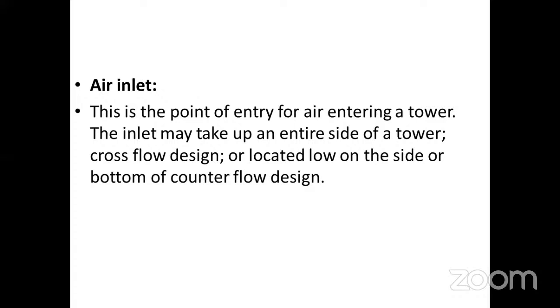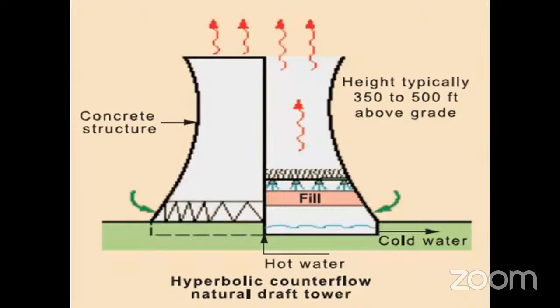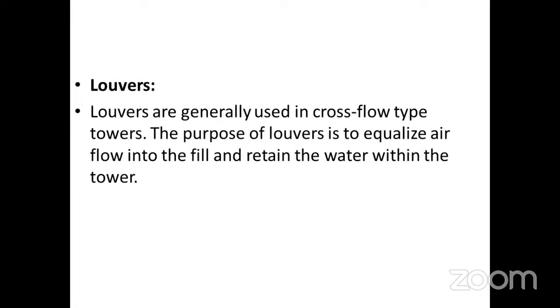The air entry point. This is the point of entry for entering a tower. Actually, in this place, there should not be any buildings or even trees which would otherwise obstruct the air flow into the bottom of the tower. Cross flow design. All these things depend upon the types of tower. Structure and all, we have seen this already. Water louvers. The louvers are generally used in cross flow type. The louvers are usually, sir, found only in mechanical type, that is conventional type. It is not used in the natural draft cooling tower. The purpose of louvers is to equalize airflow into the fill and retain the water within the tower.